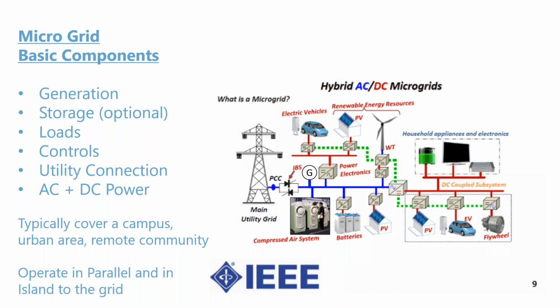The microgrid sizes can be defined by voltage level, phase, kW of peak load, kW of generation capacity, kW hours, or number of customers. The usual size of a microgrid is between hundreds of kW to a few megawatts. If a microgrid is sized between 50 to 100 kW, we can call it a nanogrid. If a microgrid is sized less than 50 kW, it can be called a picogrid. Nanogrids and picogrids have the same components as the microgrid, but at a smaller scale. The nanogrids and picogrids are usually deployed for small commercial buildings and residential solar photovoltaic systems.